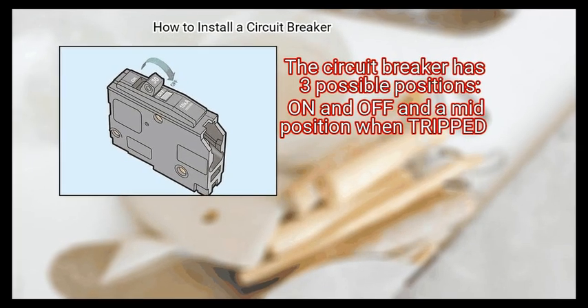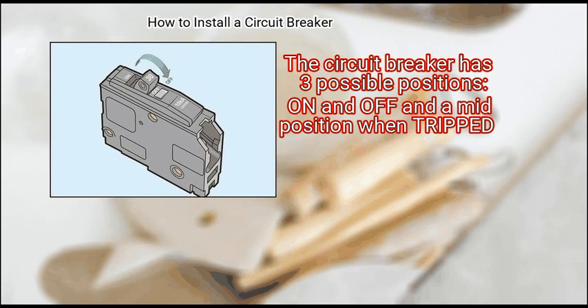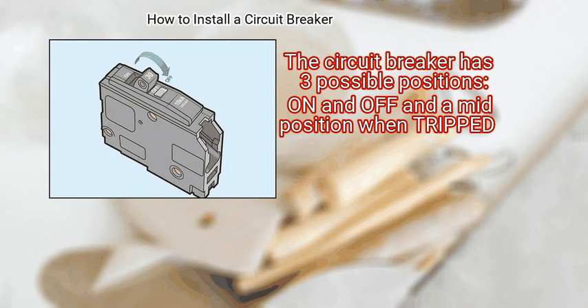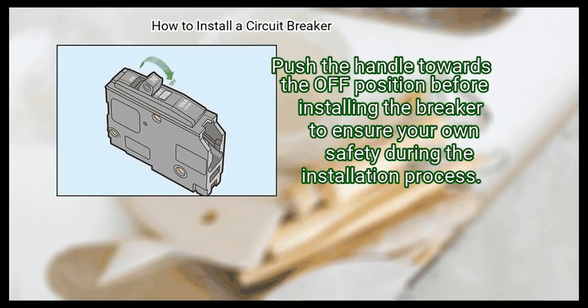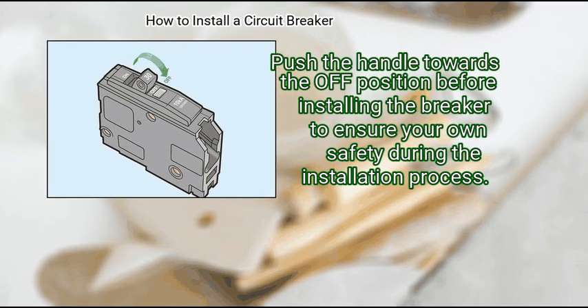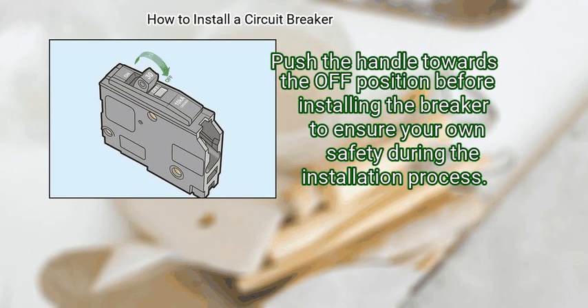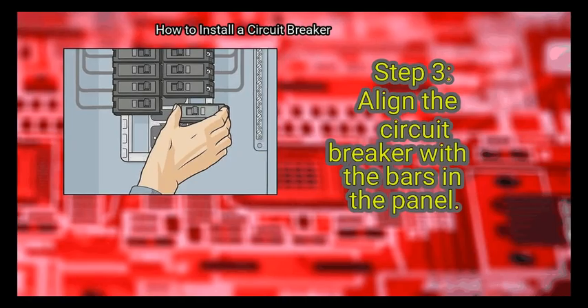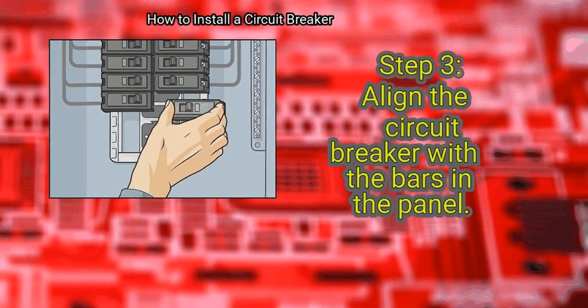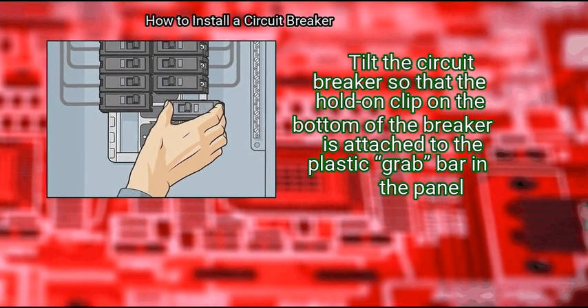The circuit breaker has 3 possible positions, on and off and a mid position when tripped. Push the handle towards the off position before installing the breaker to ensure your own safety during the installation process. Step 3. Align the circuit breaker with the bars in the panel. Tilt the circuit breaker so that the hold-on clip on the bottom of the breaker is attached to the plastic grab bar in the panel.